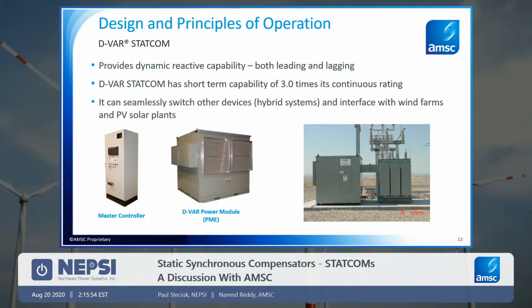On the right is a picture of an installed Statcom unit. As you can see, we step up the output of the Statcom, connected to a 4 MVA transformer through a direct bus connect, and then step the output up to the medium voltage. It could be anywhere from 11 kV up to 69 kV, depending on what the customer application requires.